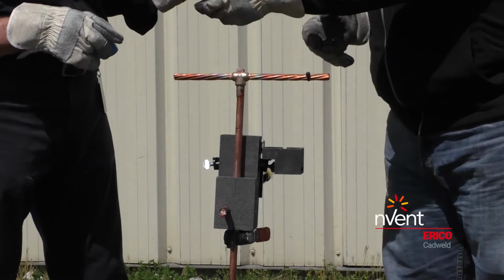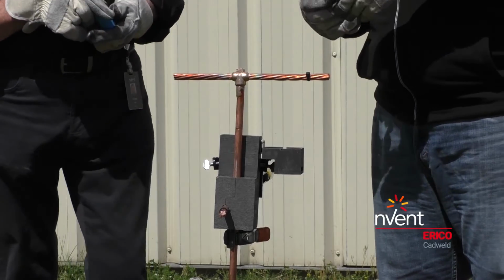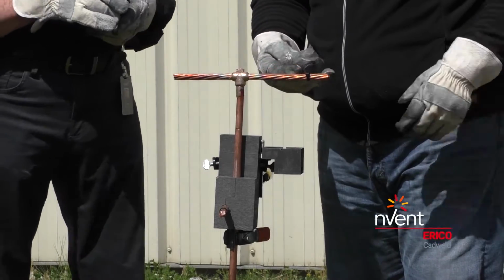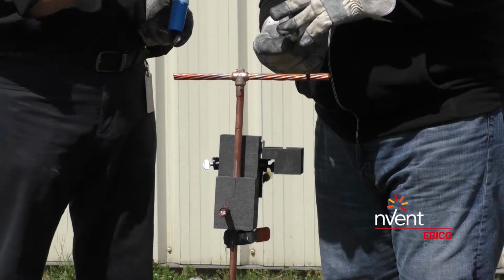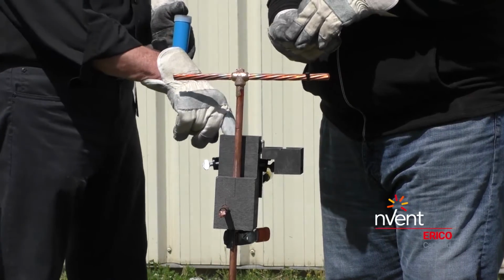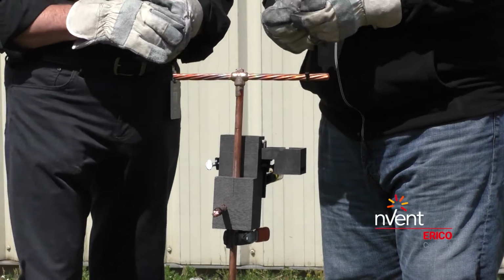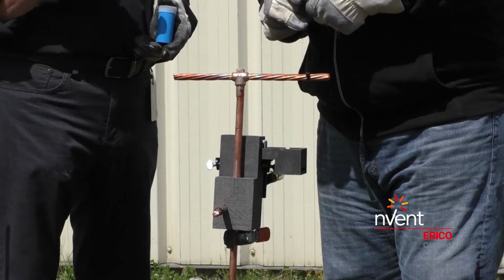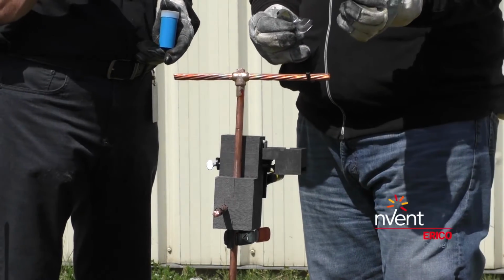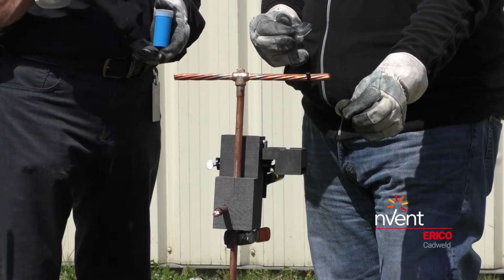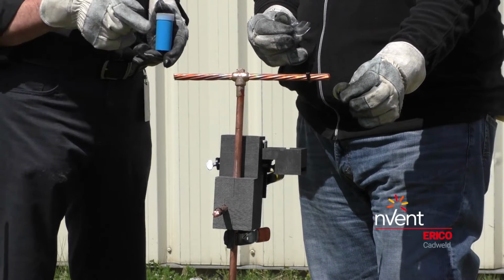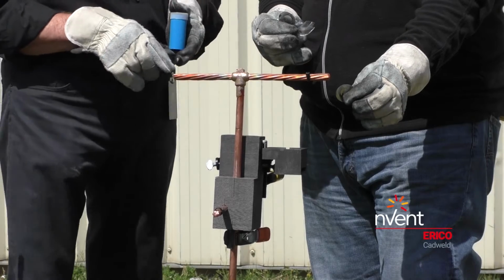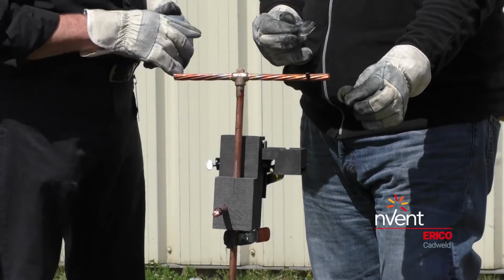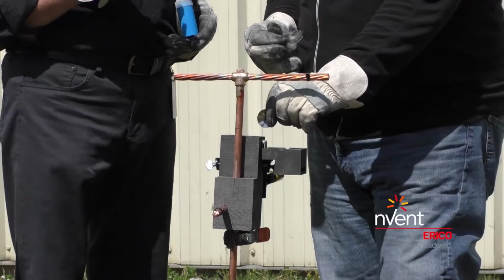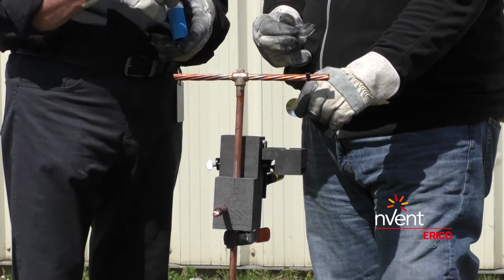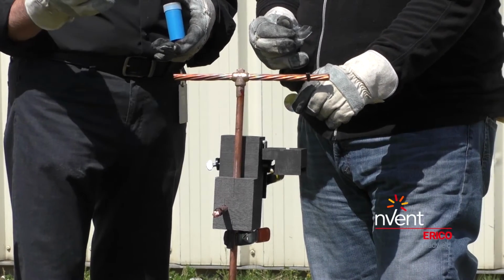Here's your disc, sir. The difference with blue tube compared to Cadweld Plus is we're using a disc. It goes into the machined part of the crucible and acts as a valve, holding all our welding material until it's completely molten. It will burn through the disc, go into the weld zone, and weld the 4-aught onto this ground rod forever. It's important to note the disc and the cup are made out of the same material, tin steel.